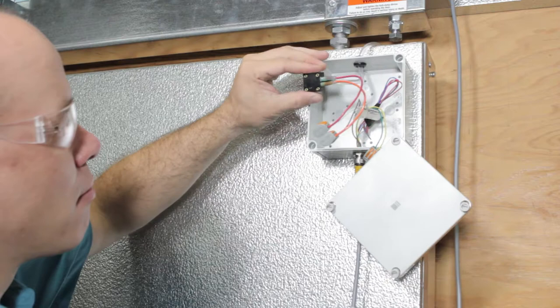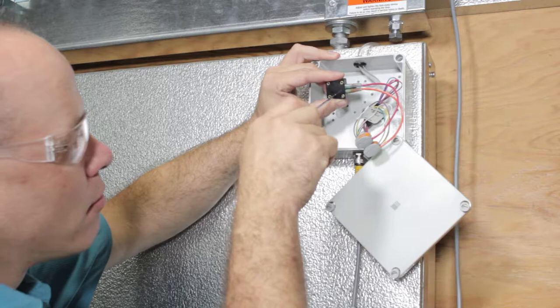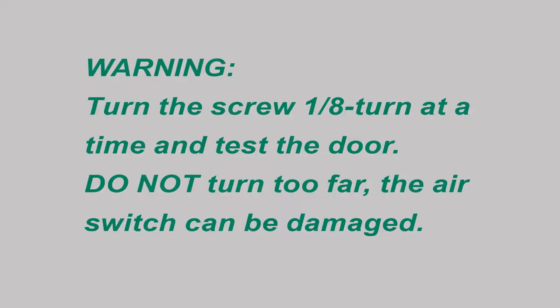Locate the air switch and using the small flathead screwdriver, turn the set screw one eighth of a turn. Clockwise increases sensitivity. Counterclockwise decreases sensitivity.